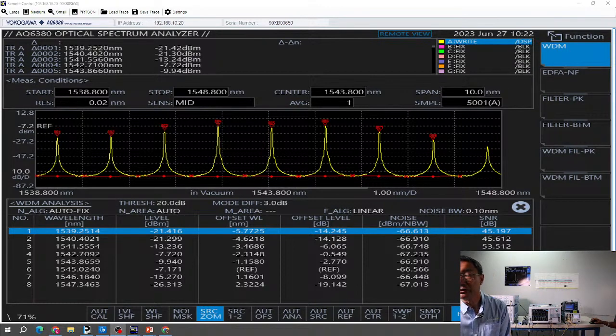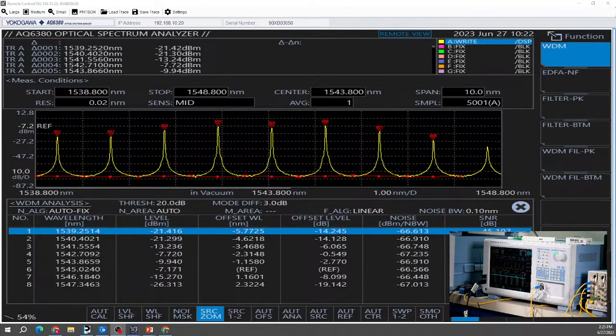How can I measure signals from my free space devices? Okay, good question, common question, actually it's a common application. A lot of our customers use our OSAs to measure the optical components like TO-can or TOSA or something like that, or maybe even a chip. So in order to do that, we do need to get the signal into a fiber.